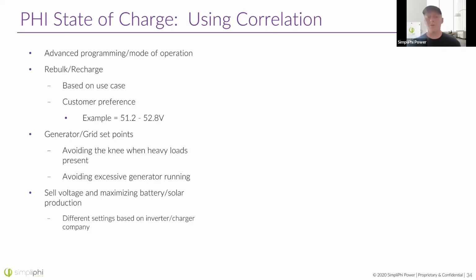Again, also what's going to affect this is the size of your load. If you've got a very small load, you'll notice that your battery won't drop to 51.2 volts until it is maybe at 20 or 30% state of charge. Whereas if you've got a very heavy load, that battery's easily going to reach 51.2 at around 50% state of charge. So this is why it's important to have a battery monitor.